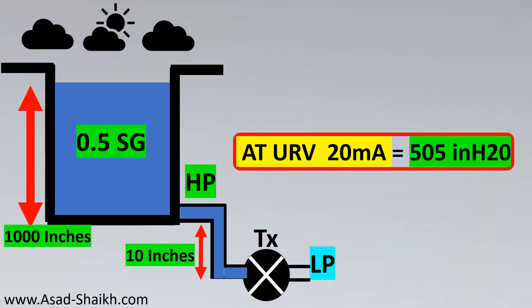You'll notice that 505 inches of H2O compensates for the 10-inch transmitter offset below the tapping. Even though the tank liquid alone gives 500 inches of H2O, the transmitter must show 505 inches of H2O to correctly account for its location.